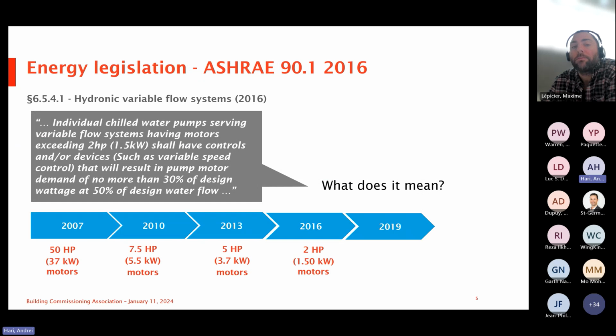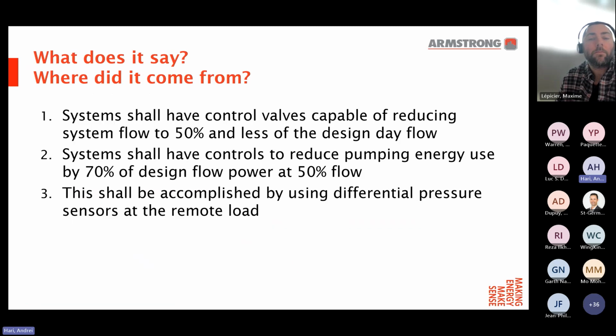But one of the things we focus on is hydronic variable flow systems. What ASHRAE was saying is that individual chilled water pumps serving variable flow systems having motors exceeding 2 horsepower or 1.5 kilowatts shall have controls and/or devices, such as variable speed control, that will result in a pump motor demand of no more than 30% of design wattage at 50% of design flow. So that's a lot of verbiage. And I always say, well, what does that really mean? Basically, what ASHRAE was saying is that you need to have a control valve that's capable of reducing the system flow to 50% and less of the design day flow requirements. So a valve reducing the flow to 50%.